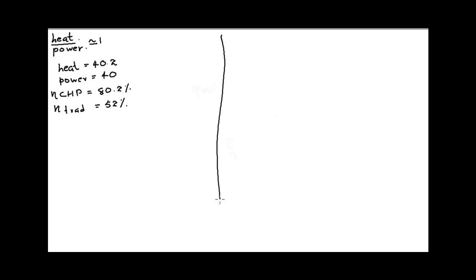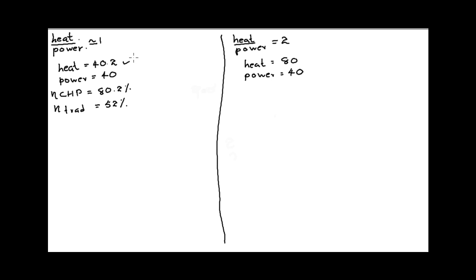Now let's see what is going to happen if the heat-to-power ratio is increased up to 2. Here, the heat requirement is about 80, while the power requirement is maintained at 40. For simplicity, if we are going to use the same CHP plant or the same diesel engine, it will give us 40 heat units and 40 power units.